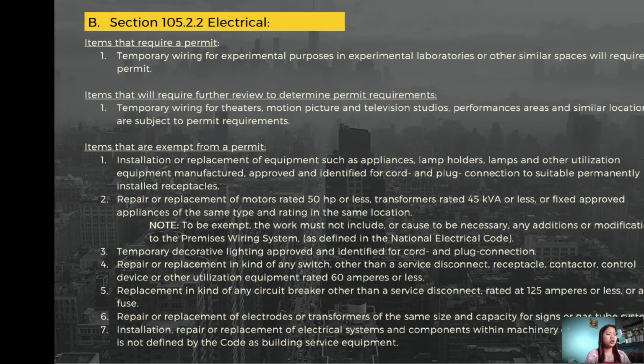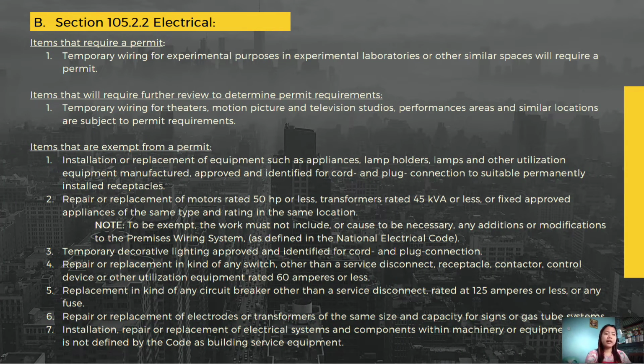Next, let's go to section 105.2.2 Electrical. Items that require a permit are temporary wirings for experimental purposes in experimental laboratories or other similar spaces. Items that will require further review to determine permit requirements are those temporary wiring for theaters, motion picture and television studios, performance areas, and similar locations. While items that are exempt from permits are installation or replacement of equipment such as appliances, lamp holders, lamps, and other utilization equipment manufactured, approved, and identified for cord and plug connection to suitable permanently installed receptacles. Next is repair or replacement of motors rated 50 HP or less, transformers rated 45 kVA or less, or fixed approved appliances of the same type and rating in the same location.